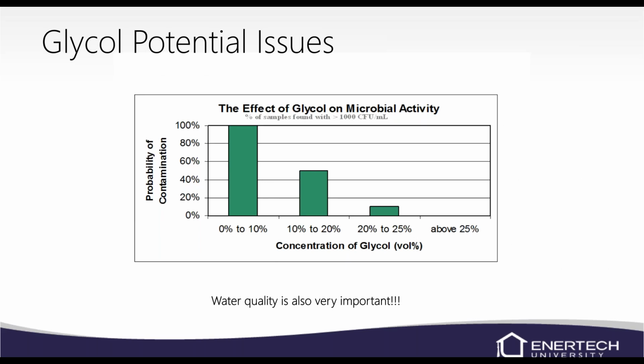Here is the potential for microbial activity in a propylene glycol system. Anything 0 to 10% glycol concentration, and you've almost got a 100% chance that bacteria will grow. From 10 to 20%, it drops to about a 50% chance of that growth happening. 20 to 25% glycol, and you've got about a 10% chance of it growing. Anything above 25%, and you're good. But we don't want anything above 30% glycol because it'll cause pumps to fail and your heat transfer will be poor. So glycol has a fine window.